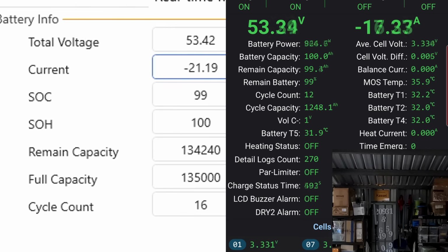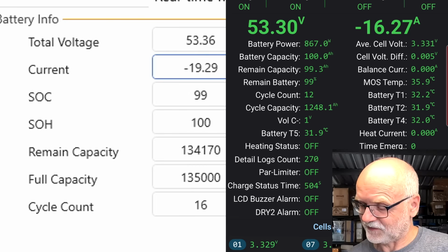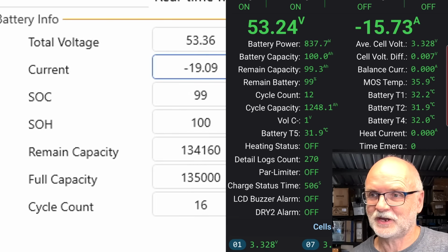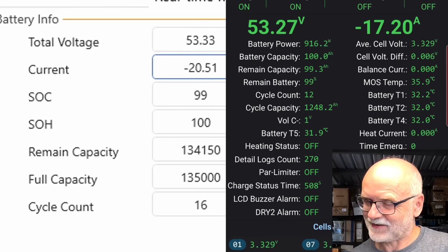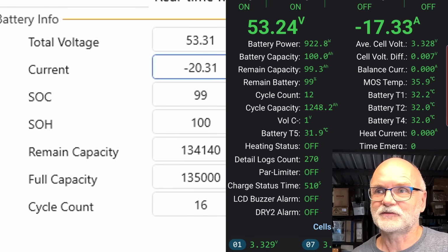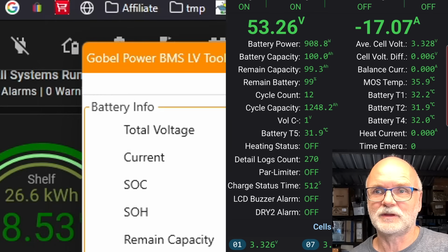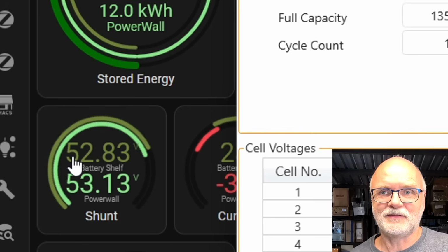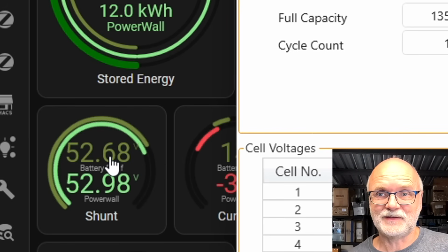Alright, battery shelf is back in action. You can see the discharge current of the Gobel Power and JK battery wasn't as high as expected, because the voltage was already down to 53.6. And we can see here in the battery shelf we've got 52.8 now, which is what it measures at the DC bus, not far away from the 53.6.